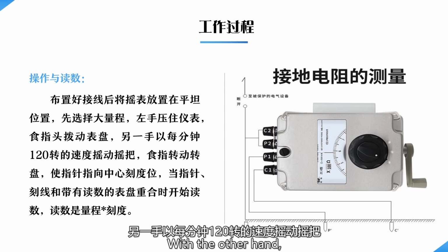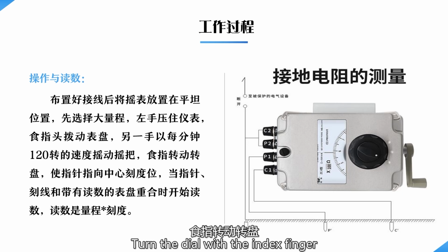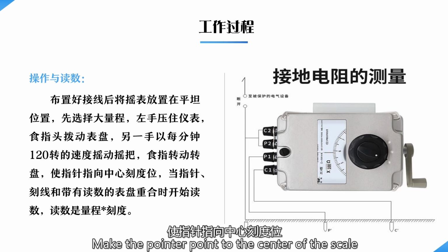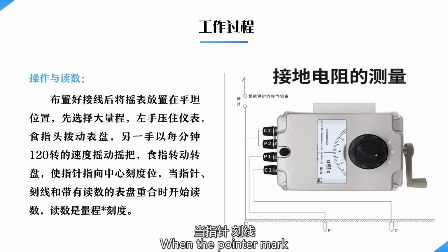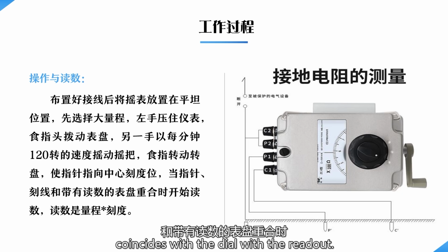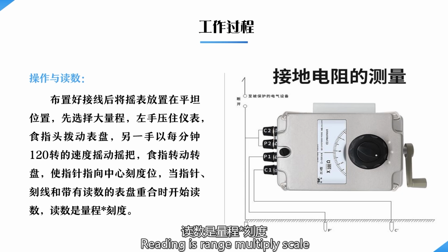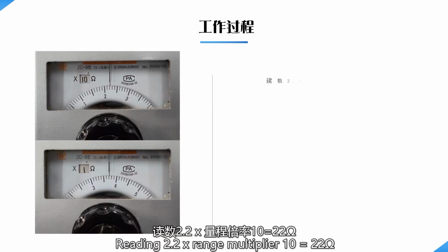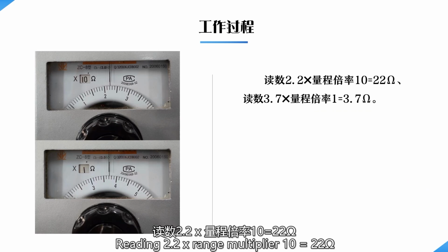With the other hand, crank the meter at 120 revolutions per minute. Turn the dial with the index finger to make the pointer point to the center of the scale. When the pointer coincides with the dial, take the reading. The reading is range multiplied by scale. For example, reading 2.2 with range multiplier 10 equals 22 ohms.